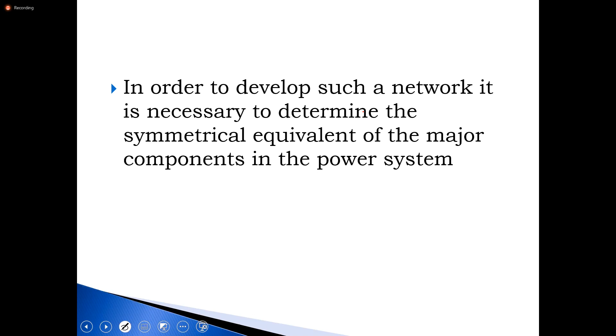So as I said just now, we need to look at how we represent each major component in the power system, right? And then we get our equivalent network, and then we find our voltage and current. Okay? All right, so we're going to start out by looking at our generators. So for your synchronous generator, where the phase voltage EA equals EB equals EC, in other words, they are balanced. Yes. And Z1, which is your positive sequence impedance, is equal to X double dash D.